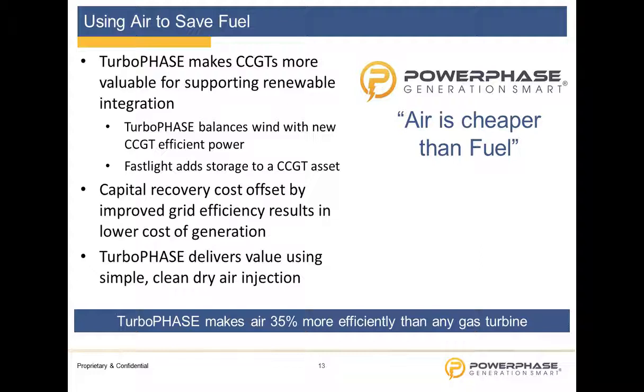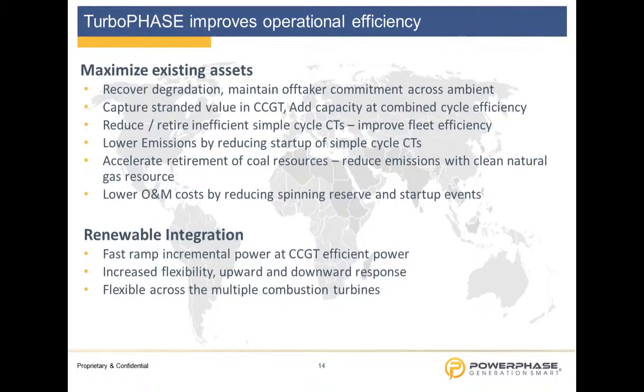And what is meant by that is we make air more efficiently than the gas turbine makes air because we're an intercooled compression cycle. If you go back to an enthalpy diagram, TS diagram, you will see that intercooling process is more efficient. And when we do that, we make air, and adding more air is cheaper than putting in more steel to burn more fuel. And with that is our air is being produced, like I said, about 35% more efficiently than the gas turbine makes air. And this allows us to improve the grid efficiency and lower the cost of generation. Interesting enough, that board member, which was our former Chief Technology Officer of GE Corporate for about 20 years, a gentleman named Dr. Mark Little, who recently joined our board, basically coined that phrase for us.